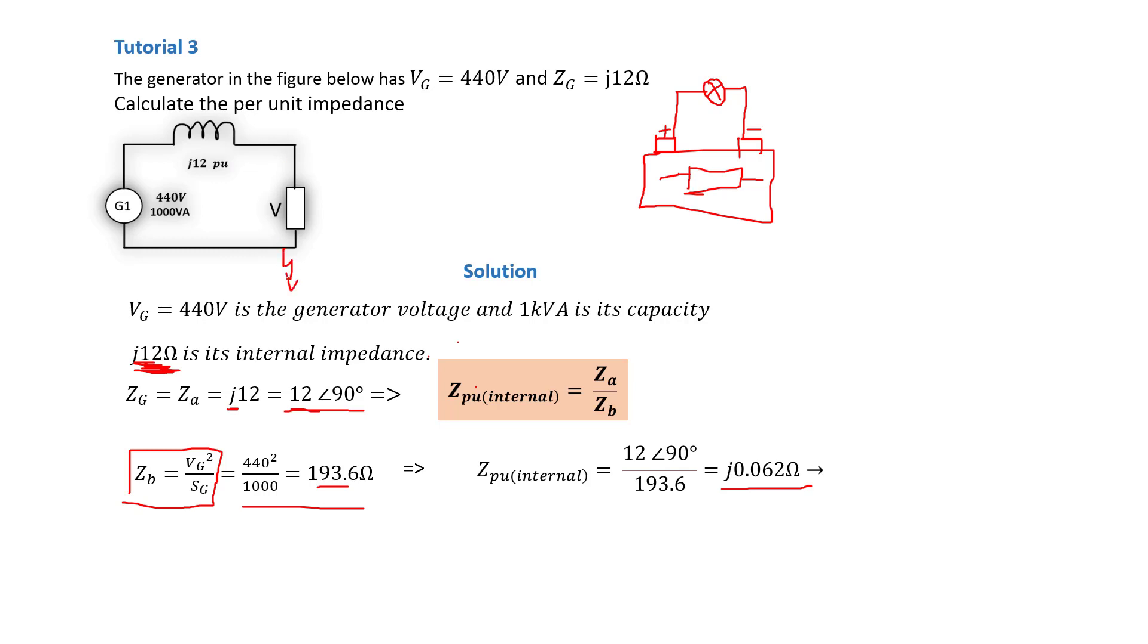In case we have a short here, you'll know how much current will flow based on this per unit because you can use the per unit formula to calculate the current, which will be 1 over Z_per unit total. So in this case, 0.062 is the total per unit from this generator here. So we know that the generator is purely inductive.